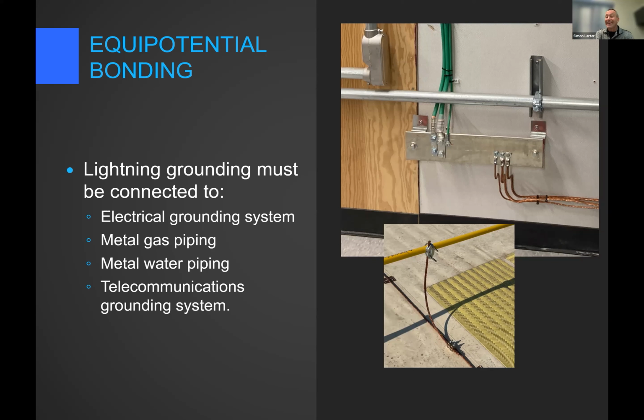And that's equipotential bonding. To be clear, we are not using the electrical ground to ground our lightning protection. We are not using the gas pipe, we are not using the water pipe. All we are doing is making an equipotential bond to make sure that everything stays at the same potential in the event of a lightning strike. If there's no potential difference, there's no chance for current flow.